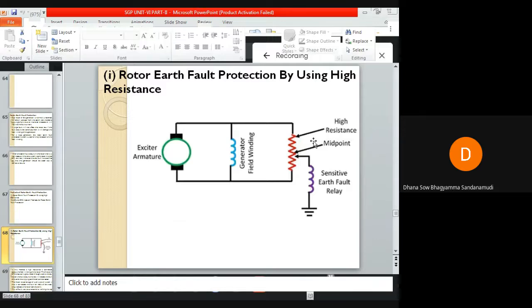In this method, a high resistance is connected across the field winding of the generator. The midpoint of this resistance is grounded through a sensitive relay, a sensitive earth fault relay, as you can see here. So when a fault occurs, this relay will detect the fault and send a tripping command to the circuit breaker. The major advantage of this type of system is that it can detect the fault for most of the rotor circuit, except the rotor center point.